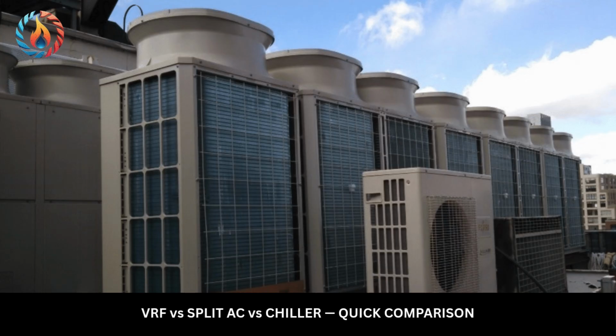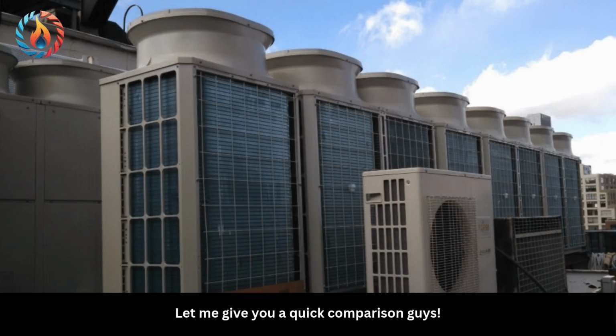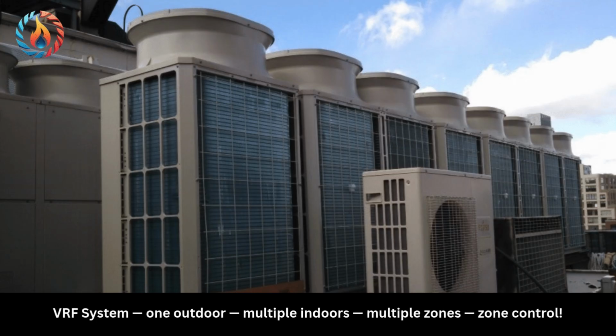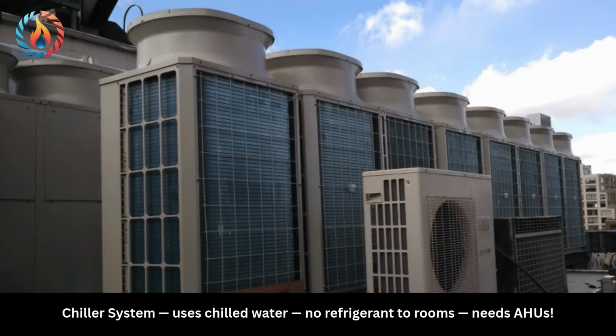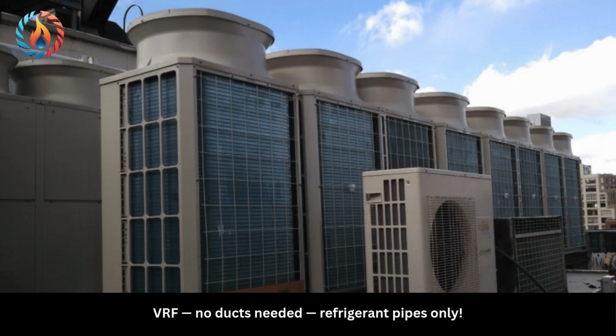VRF versus split AC versus chiller. Quick comparison. Let me give you a quick comparison, guys. Split AC, one outdoor, one indoor, one room only. VRF system, one outdoor, multiple indoors, multiple zones, zone control. Chiller system, uses chilled water, no refrigerant to rooms, needs AHUs. VRF, no ducts needed, refrigerant pipes only. Chiller, needs ducts or fan coil units in every room.